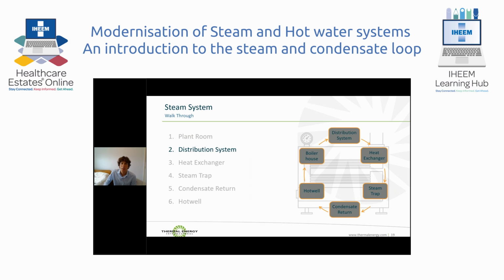We now move on to the next stage in our system, the distribution system. Distribution losses typically account for around 10% of the steam produced. Steam is typically distributed at the boiler pressure, which is normally 6 bar, where there's no requirement for higher temperature steam in the system. If there's a laundry or other facility on the site that requires higher temperature steam, it may be as much as 10 bar. The reason we distribute steam at relatively high pressure is we then reduce the volume. It's a gas. As we pressurize it, it takes up less volume, so we can use smaller pipe, reducing installation cost and heat losses through reduced surface area.